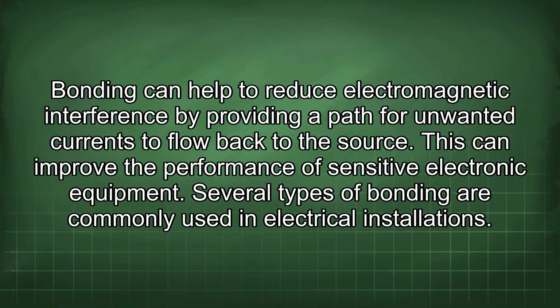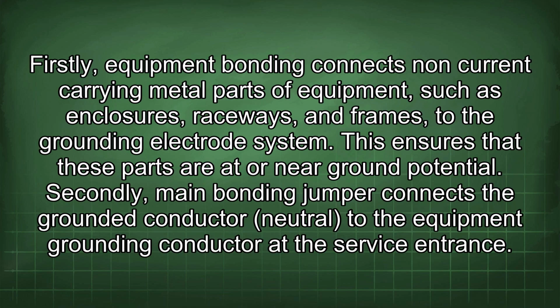Bonding can help to reduce electromagnetic interference by providing a path for unwanted currents to flow back to the source. This can improve the performance of sensitive electronic equipment. Several types of bonding are commonly used in electrical installations. Firstly, equipment bonding connects non-current carrying metal parts of equipment, such as enclosures, raceways, and frames, to the grounding electrode system. This ensures that these parts are at or near ground potential.